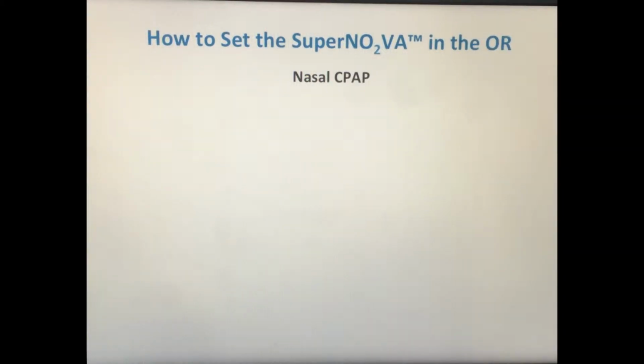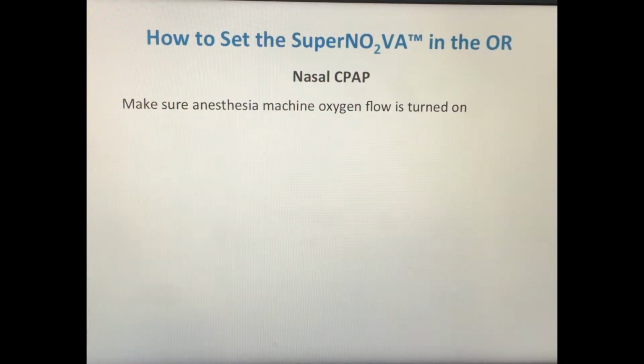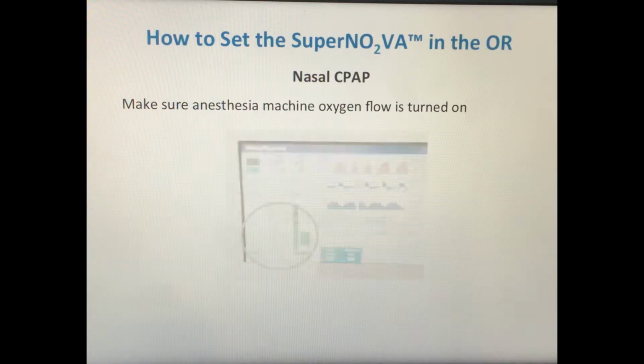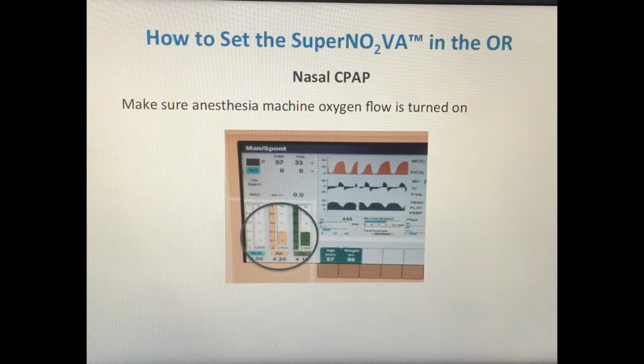Let's first start by showing you how to set the SuperNO2VA up in the OR for nasal CPAP. The first thing that we need to make sure is that the oxygen is turned on. In order to do that, we want to look at the anesthesia machine and make sure that there is flow going into the flow meter. Here in green is oxygen. This means that oxygen is actually flowing into the anesthesia machine to the patient.